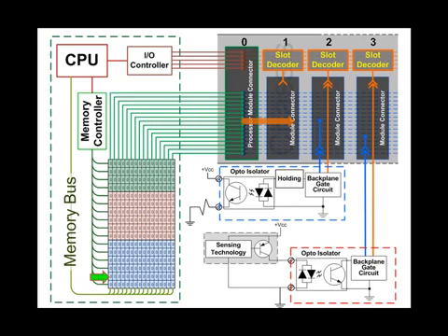All 16 backplane gate circuits are activated simultaneously on that one module, and the output image is felt at the holding circuits of all 16 outputs, and the output devices are switched on or switched off to match the output image transferred out from the memory location O:2.0 to the output module in slot number 2.